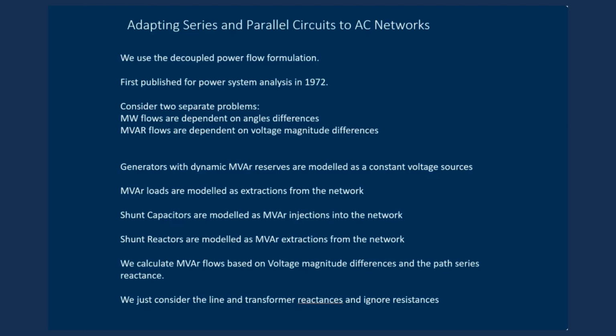So we've had the concepts around for a long time, but we really haven't followed through and provided you with the operating tools to put those concepts into practice and make quantitative assessments. By that I mean how much megawatts will flow on this path versus another path, or how much voltage magnitude difference is needed to support a megavar flow. In the voltage support networks that we'll be developing, we'll consider generators with dynamic megavar reserves as constant voltage sources. Those generators are holding those regulated voltages, which may be either on the low side or the high side, at a constant value as long as they are within their megavar limits.